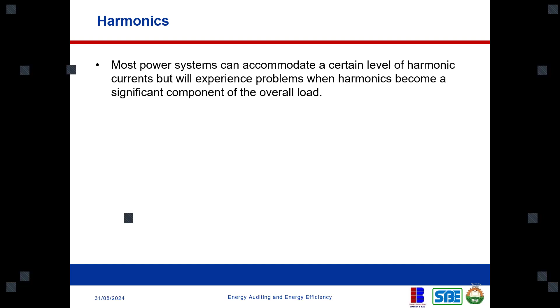As these higher frequency harmonic currents flow through the power system, they can cause communication errors. For example, in places with Internet of Things or automation systems, it sometimes affects the functionality of these automated systems because the signals they get have been distorted. Some automated equipment uses the footprint of the electrical system to operate, so once that footprint is distorted, it creates confusion and distortion in the process. Sometimes it can cause overheating of the hardware, metering errors, and so forth.